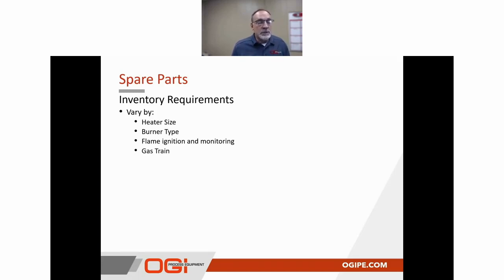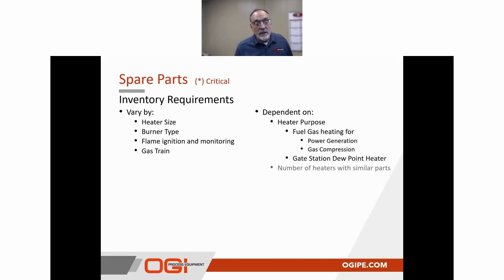One thing that you're going to see throughout this portion of the presentation is that if there's a critical spare that we feel is important, we've identified that with an asterisk or parenthetical indication at the end of each of those. And we understand that spare parts inventories will vary based on the purpose of the heater and the process, whether it's a fuel gas heater for power generation or gas compression, or maybe it's just a gate station heater, something that just supports dew point operation under a regulating system. It can also depend on the number of similar types or styles of heaters that you have in your gas distribution system, the distance or proximity to a centralized parts inventory, or in some cases it could just be company preference or policy that says we will or we will not maintain these spare parts.